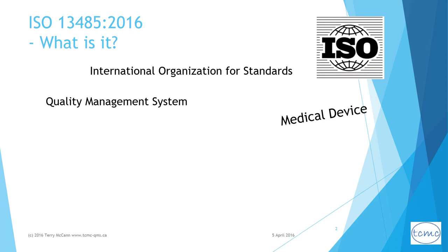By certifying an organization as conforming to the ISO 13485 standard, an accredited third-party body of auditors attests to the organization conforming to the quality management requirements of the standard, including being compliant with applicable regulatory requirements, which must be identified within the Quality Management System, or QMS. If you are not sure what a quality management system is, please have a look at my video, What is a Quality Management System?